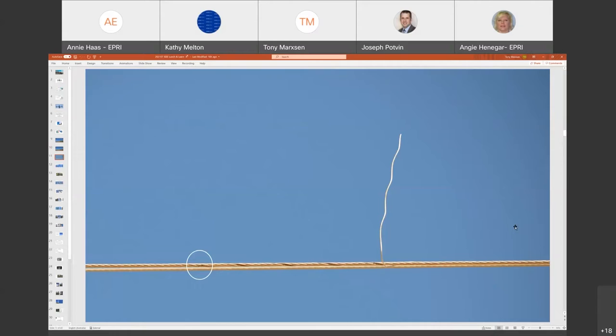This is a close up of the same thing, and you can see there are multiple broken conductor strands here. One of them is progressively unraveling, and that would continue to unravel until it was long enough to reach the phase next to it, in which case it would disappear in a bright flash and a shower of molten metal onto the ground below.